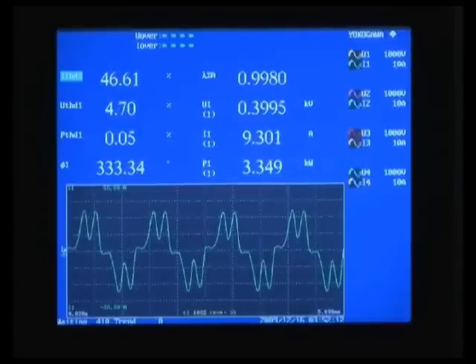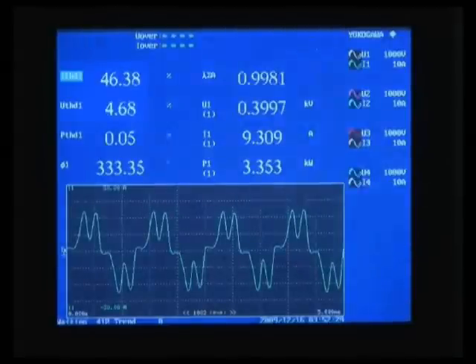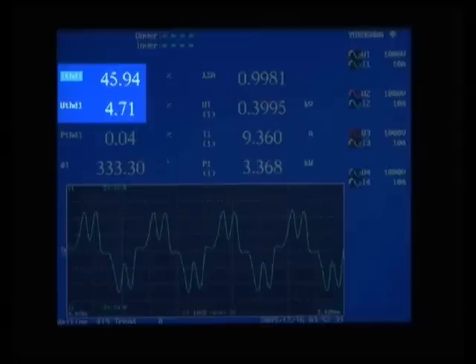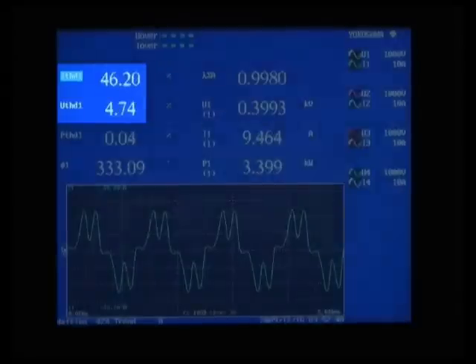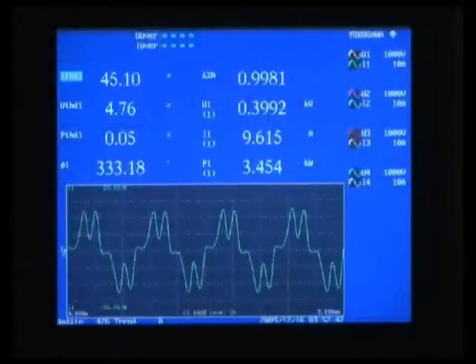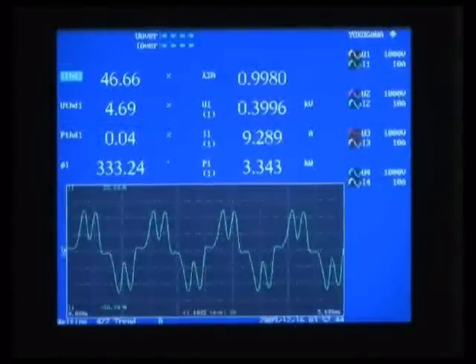And what you're seeing right now is a real-time waveform with the current and voltage harmonics being displayed in the upper left-hand corner. You'll note that with a 6-pulse input on this distribution system, we're seeing in excess of 40% current distortion and almost 5% voltage distortion. The waveform that's present is anything but sinusoidal.